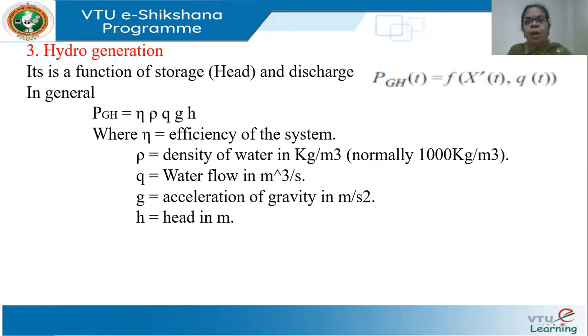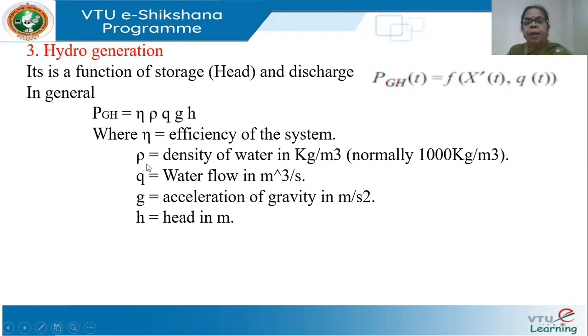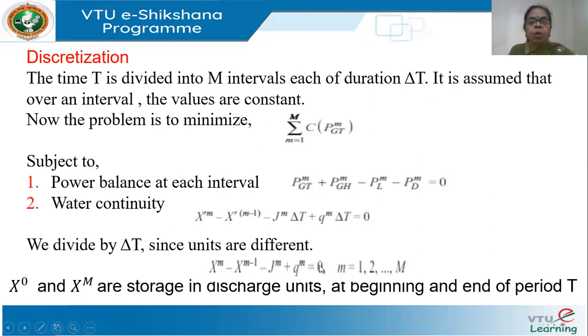The third constraint is on hydro generation. The power generated by a hydel plant is a function of storage and discharge. In general, PGH = η·ρ·q·g·h, where η is efficiency, ρ is the density of water (approximately 1000 kg/m³), q is water flow in m³/s, g is acceleration due to gravity, and h is the head of water available in meters.